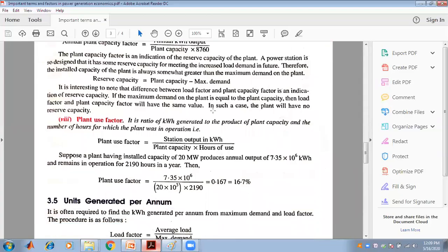The plant use factor is the ratio of kWh generated to the product of plant capacity and the number of hours for which the plant was in operation. For example, a plant with an installed capacity of 20 MW that produces an annual output of 7.35 × 10⁶ kWh and remains in operation for 2,190 hours gives a plant use factor of 7.35 × 10⁶ divided by (20,000 kW × 2,190), which equals 0.167 or 16.7%.